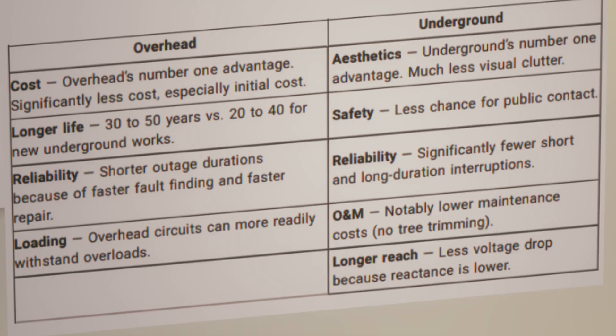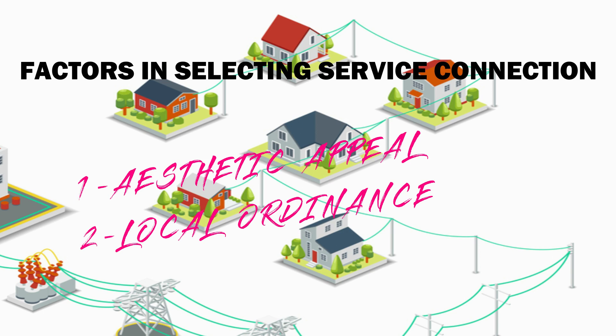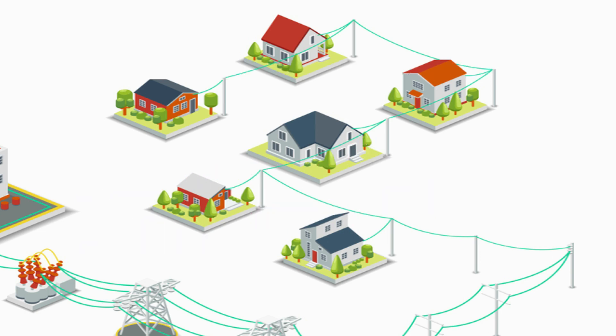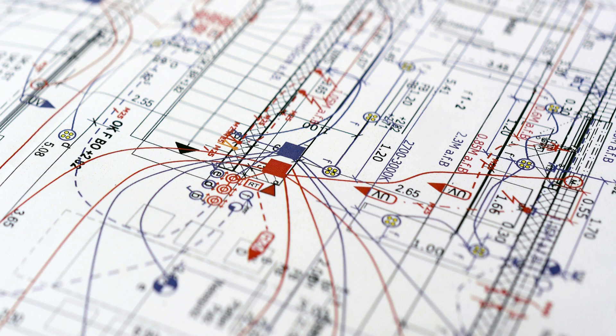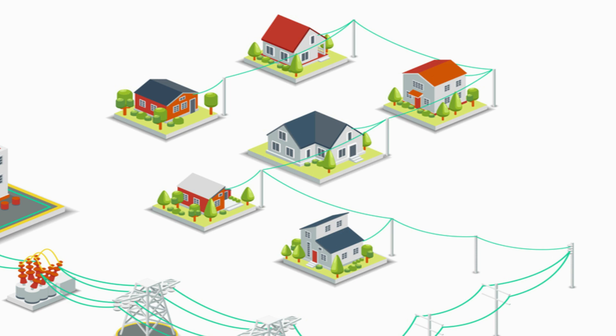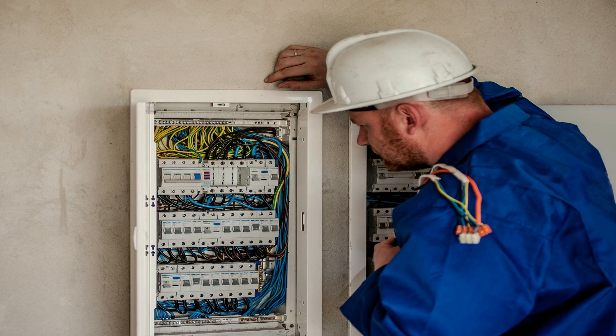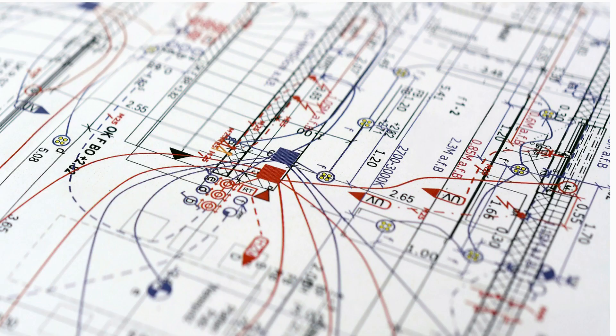Underground cables almost cost twice that of overhead cables. Overhead wiring systems are thus the most common in rural areas. Local ordinance is also a factor when selecting between these choices. As an electrical engineer, you must properly size the service cable while designing. The cable size will be derived from the building connected load, which is derived from the load calculation done for the project.